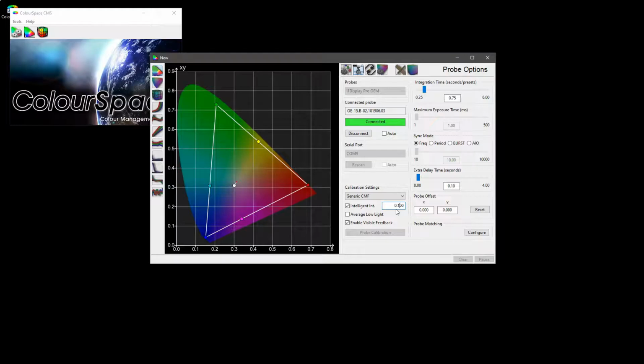If there is a difference, it will take another patch reading with an even longer integration time and compare that to the previous one. And it will do that repeatedly until it hits the maximum integration time for the given probe. At that point, that last reading will be the one that it will accept as being the most valid it's going to get. Average low light is an alternative, and basically below a set threshold will take multiple readings of the same patch and average the values.